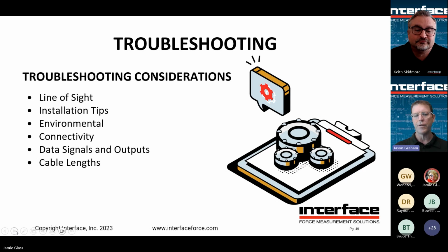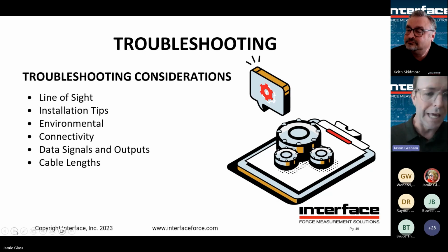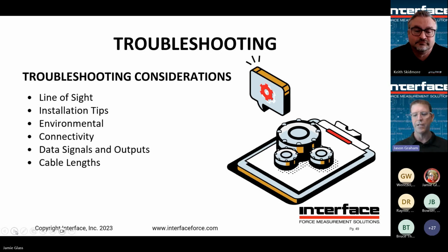Battery, there's a few different things we can look at as well with the WTS toolkit that allows us to do troubleshooting. Are you looking at your signal strength? Are you looking at your power? Are we looking at the duration of the power? Is it paired? What's the signal coming out of it? In some cases, from a cable length consideration, when it's wireless it shouldn't be a big deal, but if you have a display or something else with cables, is there something along those lines that needs to be investigated?